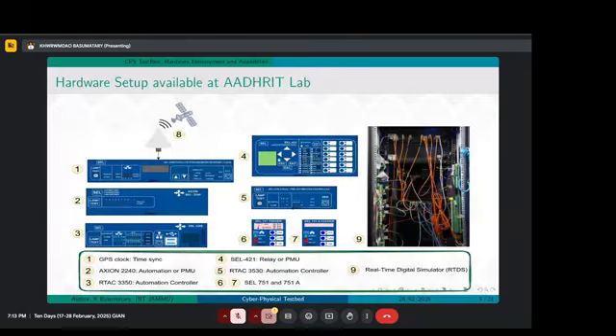And these are the hardware available that we have in the AADHRIT lab. This one, the 8 and 8 that I have highlighted here, is the GPS antenna. And this one is the real-time synchronization clock. And this SEL-2240 Axion is a real-time automation controller which can also act as a PDC and PMU. And this SEL-3350 can also act as a PDC and automation controller. And this one, SEL-421, is a transmission line protection relay, which can also act as a PMU, phasor measurement unit. And here we have an SEL-3530, that is also a real-time automation controller.